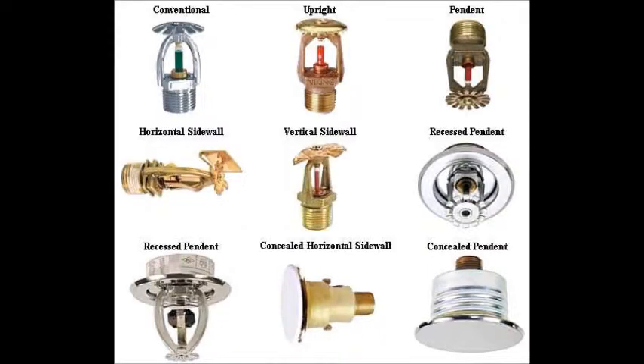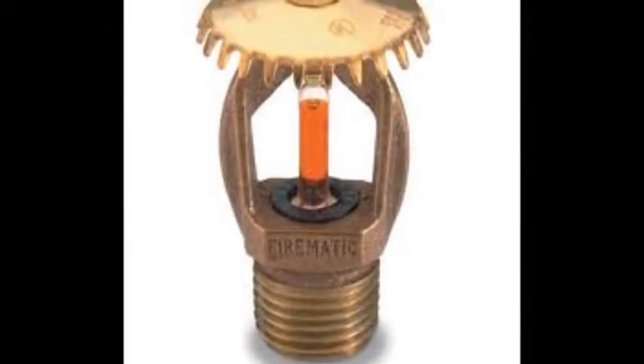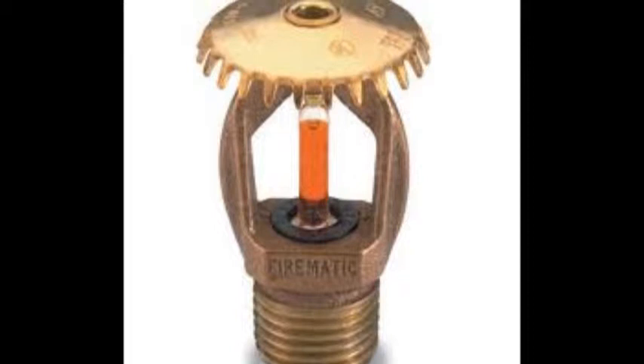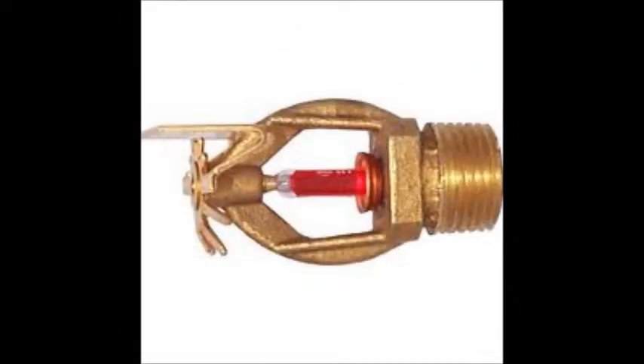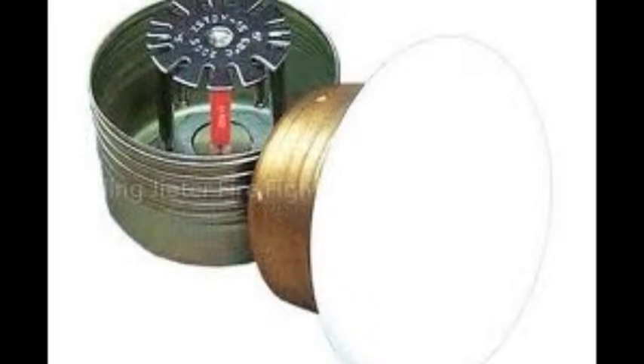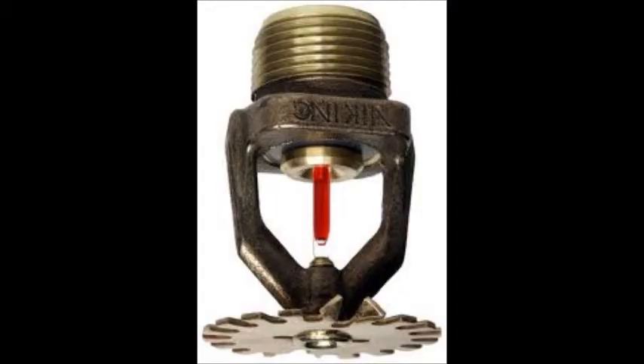There are different types of sprinkler heads, and each of them is made a specific way for different types of buildings. First of all, there are the upright sprinklers, and these are used when there are no real ceilings. Next, there are the sidewall sprinklers. These sprinklers are used when there are construction restrictions for piping in the ceilings. Concealed sprinkler heads are used in newly constructed buildings and drop before sprinkler activation temperature. Attic sprinklers are used in attic space, and pendant sprinkler heads are the most common form of sprinklers.